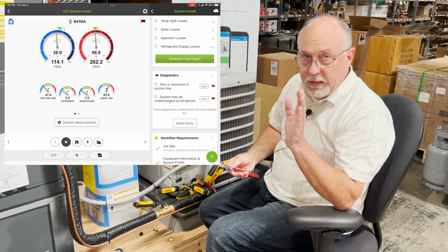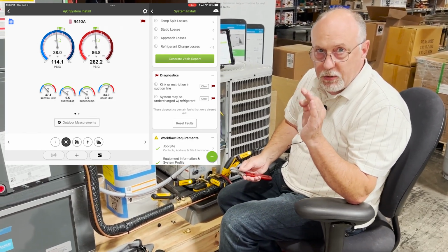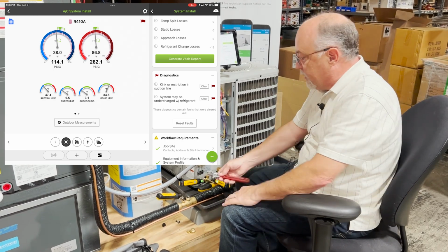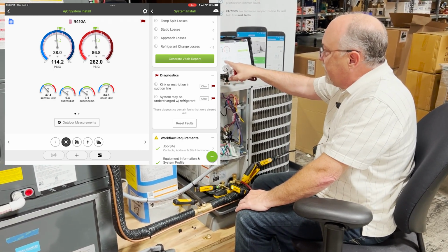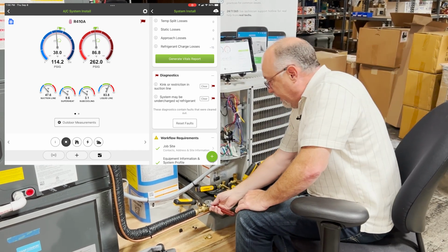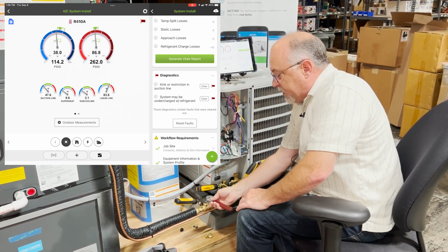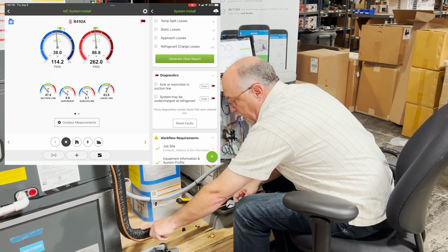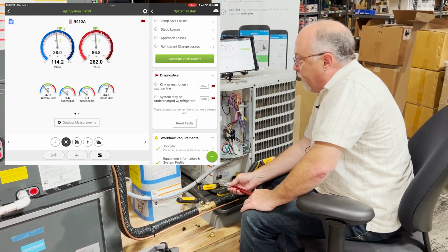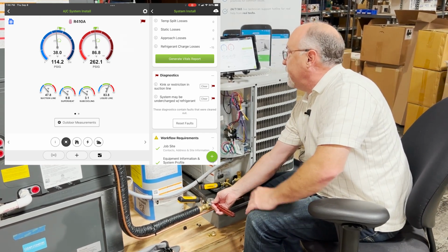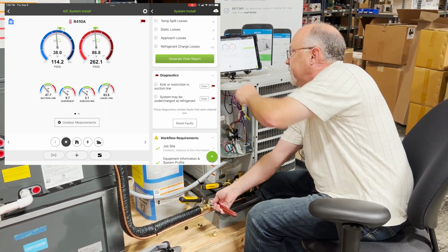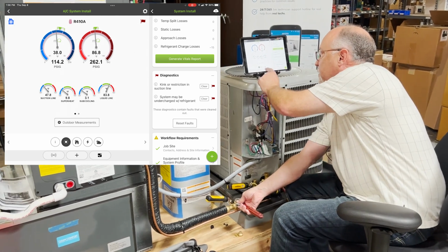One thing that you really need to watch if you're gonna do this in a classroom, by the way, is when you open this valve back up, you can see my suction pressure's low, my suction temperature's low, my superheat's running about 9 degrees right here. If I open up this valve, what's gonna happen is I have a full column of liquid here now behind this. And if I open this up really fast, I'm gonna flood my compressor. And you'll see here, just as I open this up, if you watch my superheat, it might be easiest to watch it on the graph here.